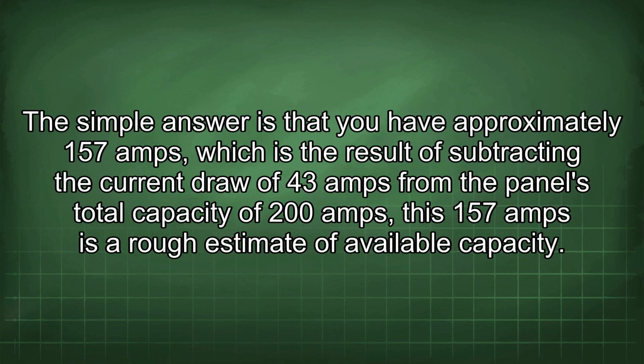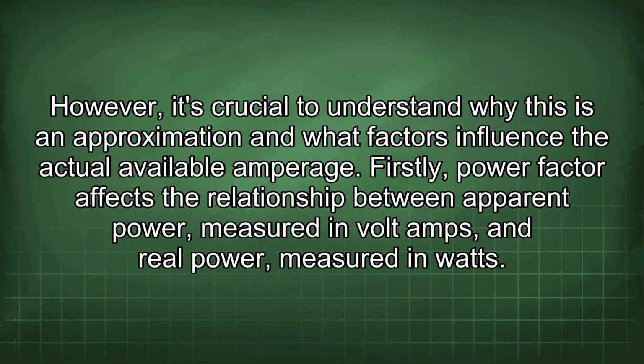The simple answer is that you have approximately 157 amps, which is the result of subtracting the current draw of 43 amps from the panel's total capacity of 200 amps. This 157 amps is a rough estimate of available capacity. However, it's crucial to understand why this is an approximation and what factors influence the actual available amperage.